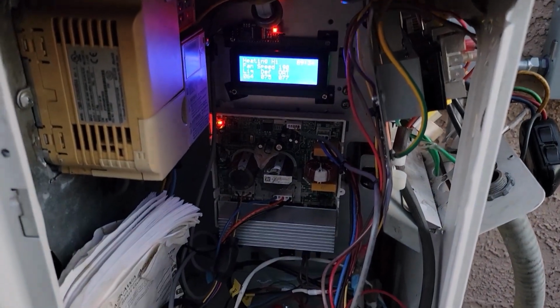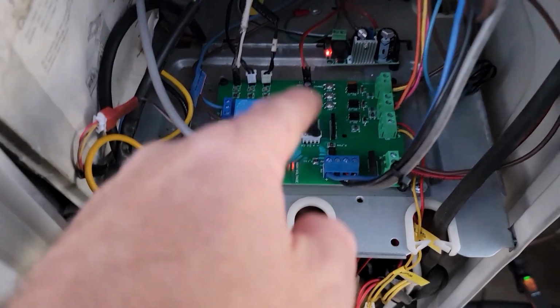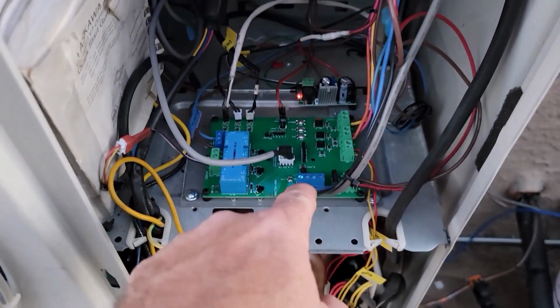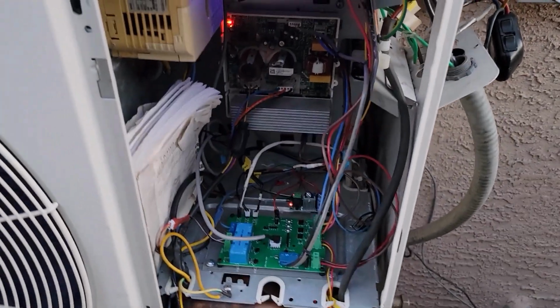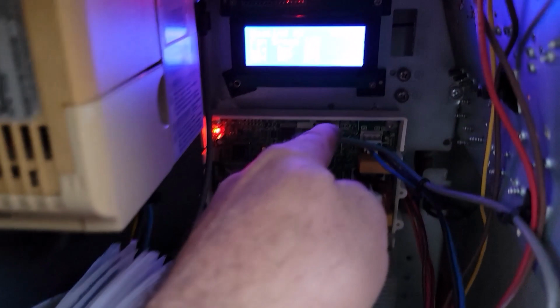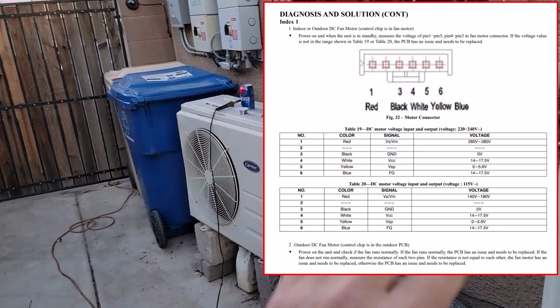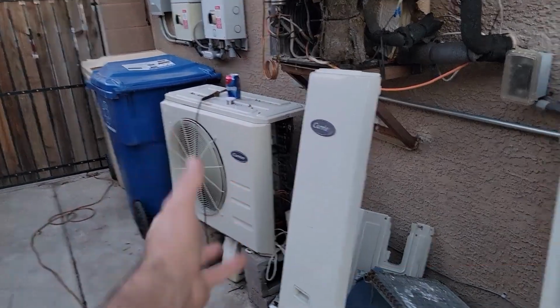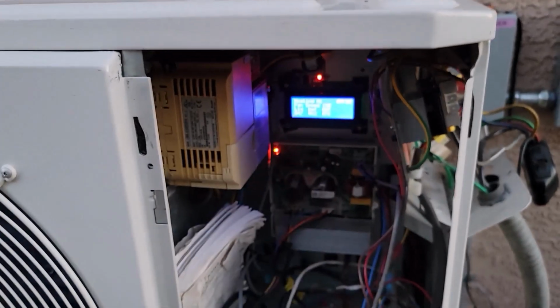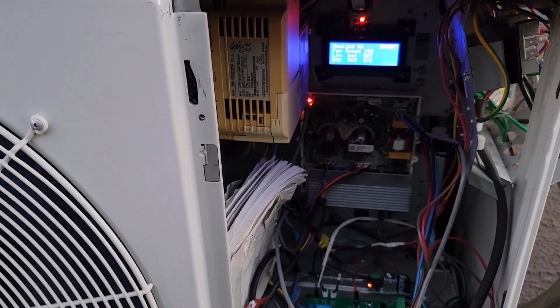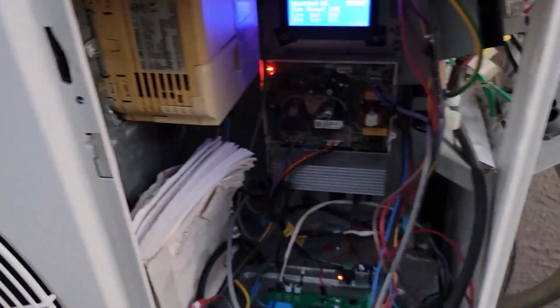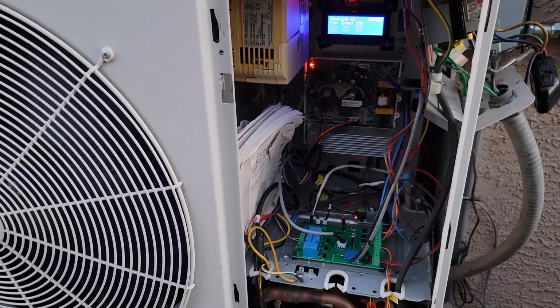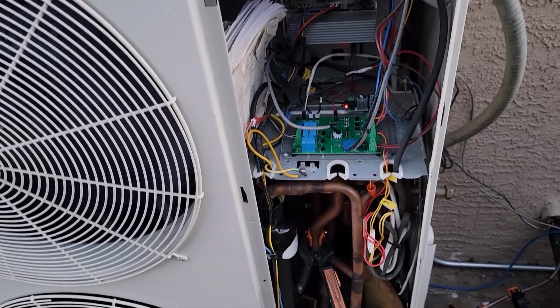But back up a little bit, okay. So this thing here is sending a pulse width, taking the 15 volts from here and reducing it, attenuating it with pulse width modulation back to the input, and that's how these fans work. I could do that with pretty much any fan, even the one with the inverter power module built into the motor, or these other types that take it here, work kind of the same. Most brands of VRF mini split stuff work like that, if it's got that external type of motor or module. But the big VRFs, that's all communication, I can't interface with that.